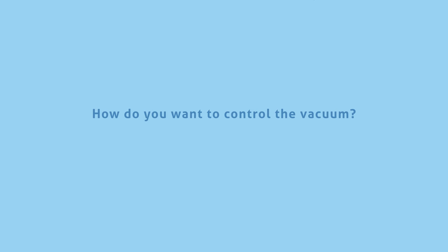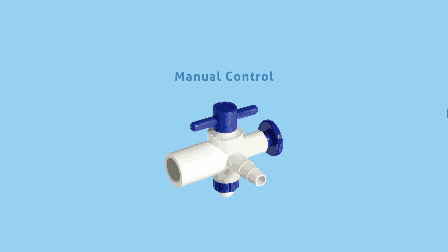There are a few options available for vacuum control. Manual control is the simplest method and involves the use of a stopcock or manual valve to adjust vacuum. Unfortunately, you'll have to monitor the vacuum closely, as vacuum requirements may change.